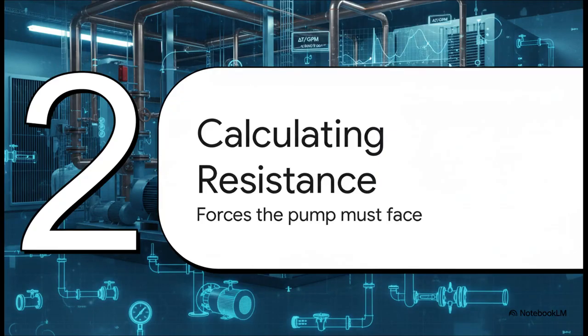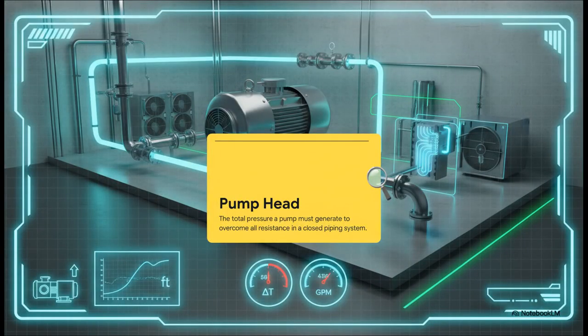Of course, pushing all that water around isn't a walk in the park. The pump has to fight against resistance through, sometimes, miles of pipe. So the real core of the design process is adding up every little bit of that resistance. And in engineering, we have a name for that total resistance. It's called pump head. Pump head is basically the total amount of oomph the pump needs to generate to shove that water through the entire system, overcoming all that resistance.